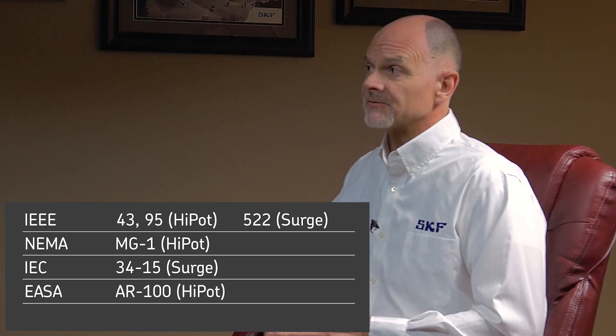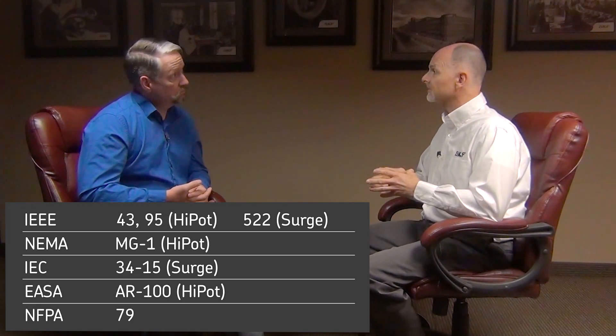Are there any standards that dictate these tests? The standards are really good news for both us as a company and you as a potential customer, because you don't have to believe me or the company I represent. The standards have been around and they're peer-reviewed — not just one company saying what you should do. These are international organizations that have been around for decades and the standards are frequently reviewed. Some of the key ones we reference are IEEE, NEMA, IEC — which is more common in Europe but has very aggressive standards — EASA, which is for the motor repair industry, and also the NFPA, the National Fire Protection Association. They all promote high voltage testing, and they're all in the same ballpark: if you're testing above operating voltage, you'll find things you simply can't find with low-voltage equipment.